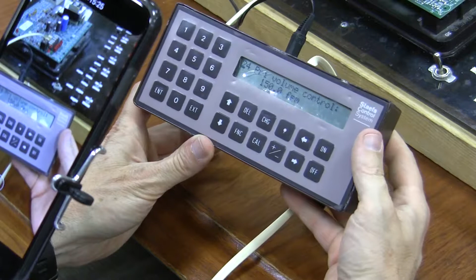So now I can see what this is, and I can go to parameter number 03, which is the actual flow he's flowing. Right now this box, just because he's sitting here on the table, he thinks he's at 293, 300 feet per minute. So he's above set point.